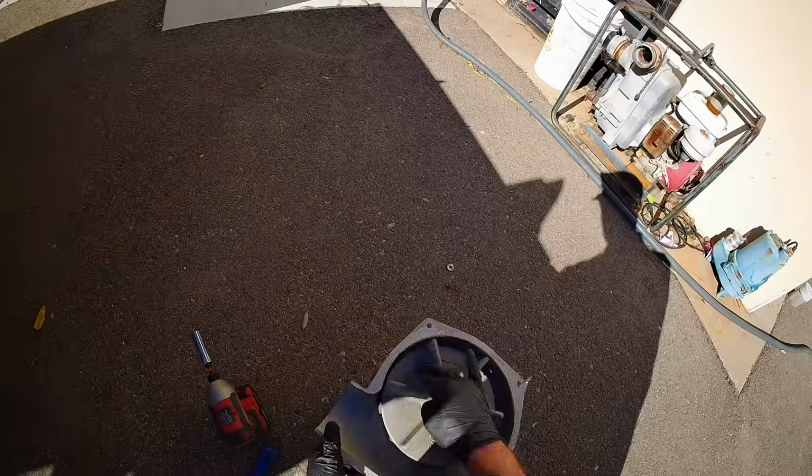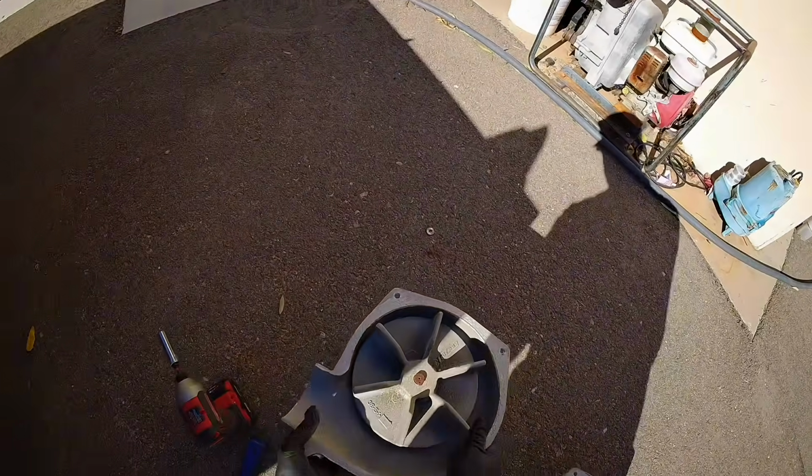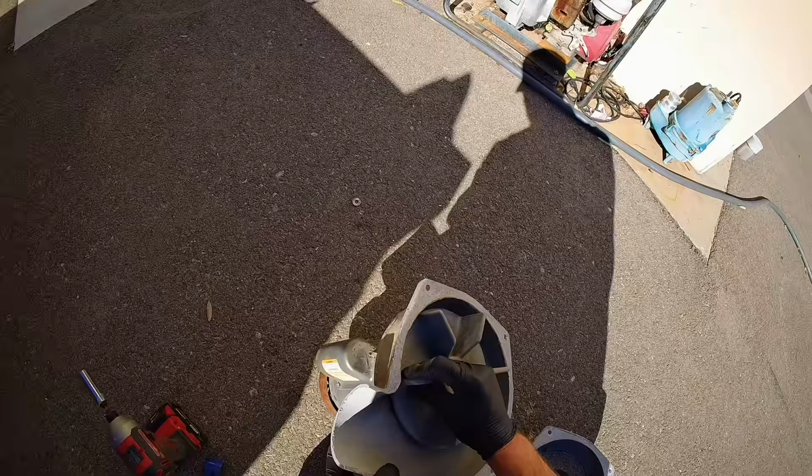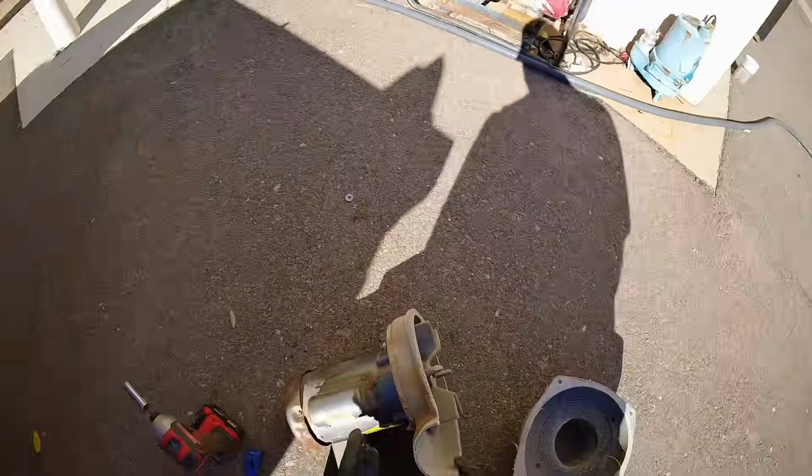So here's the impellers for the blower. As you can see, I want to point out how close they are. If you got a burr or something in here, it would jam it up. I've had that happen on other blowers. This one's a little bit more wide, but the newer ones they're getting, it's really, really tight in there. So anyway, I just want to kind of show you how it works.